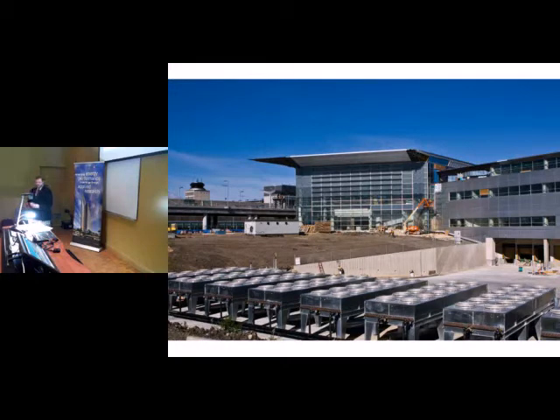So what we found is that we had to go back and reprogram all the controls to get a better balance of heating and cooling and air temperature to try to make sure that we're not freezing passengers in the morning after the building's been cooling off overnight in the summertime. And that's worked out very, very well as well. What we found was by the end of the summer, the central utilities plant was able to shut off one chiller altogether. Where we were, say, running 3 chillers, we were running the building on 2 chillers as a result of getting those systems commissioned properly. So they have lots of available cooling, and the building is making use of that very, very effectively.